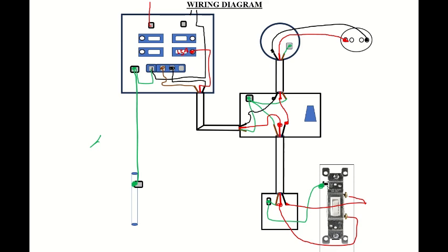Now it is preferred to put the main wire on the breaker, mainly because if you want to do an installation or an addition or any repairs to the panel, when it is on the breaker, you're able to turn it off, hence the bars are not energized. Now when you place it on the bus bars, then the bars remain energized, right? And that can be problematic, especially if you are not sure what you're doing, right?